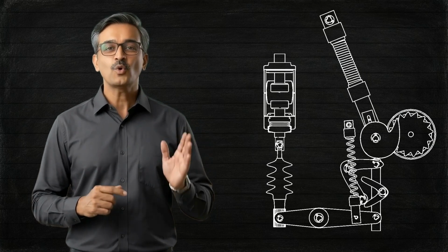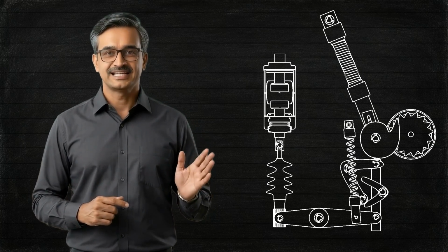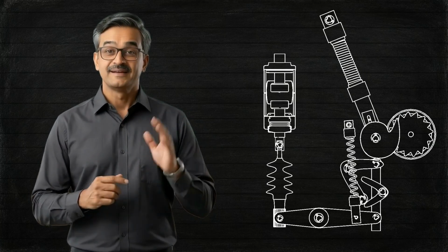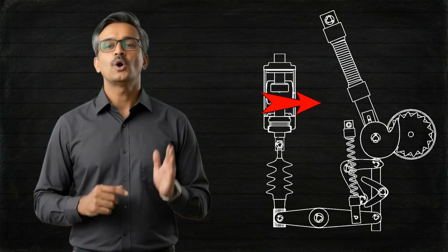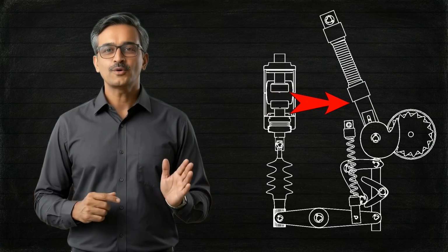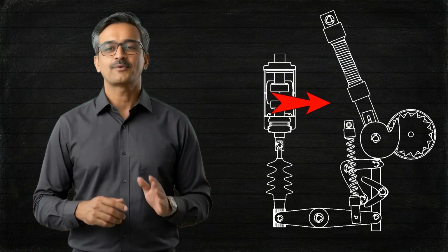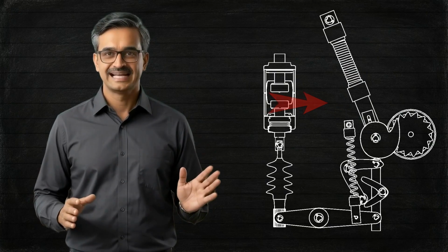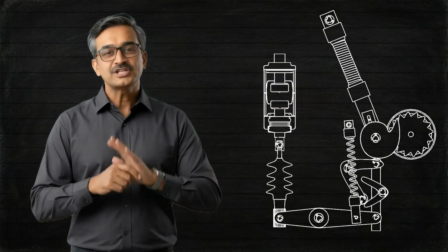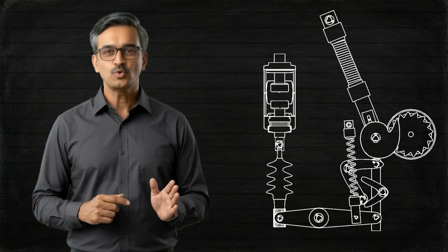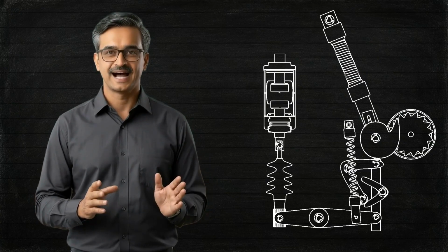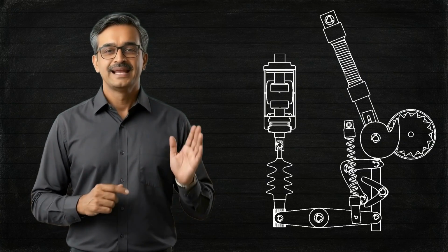Have you ever noticed what happens when a spring is released suddenly? It vibrates. Similarly, during breaker operation, the moving mechanism may experience shocks and oscillations. To absorb these shocks, oil dashpots are provided. These dashpots work exactly like the shock absorbers in a motorcycle or a car. They smooth the movement, reduce vibrations, and protect the operating mechanism from mechanical damage.